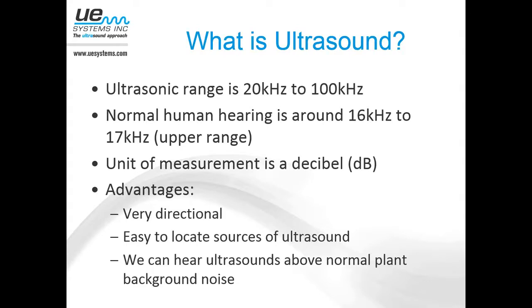And we look at two things. We either look at turbulence, which is a source of ultrasound. Typically, turbulence would be from a pressure or a vacuum leak, or turbulence can be created by electrical discharge. And we also look at friction, and that's typically what we're looking at when we talk about condition monitoring of bearings and rotating assets. It's also what we would look at from a lubrication standpoint. You know, too much friction, too little friction, and that lets us make better decisions when we know how much is there. So we can hear these sounds above any normal plant background noise, which gives it a decided advantage over using a stethoscope or using our ears.